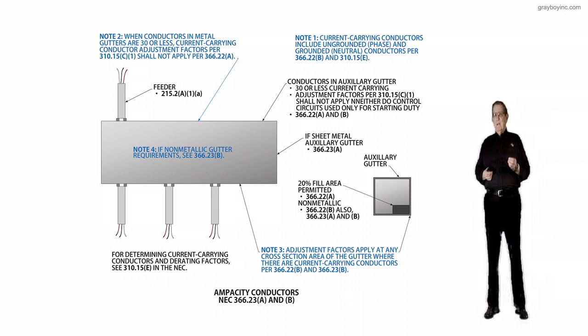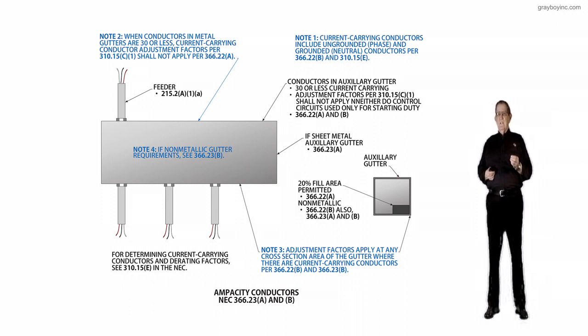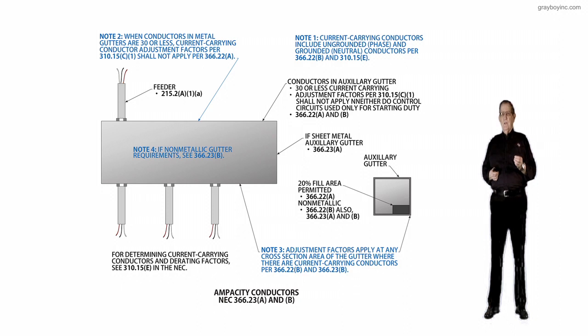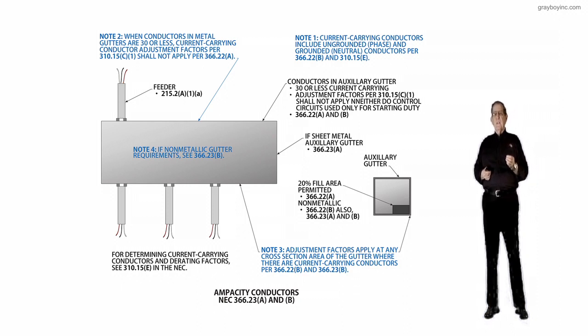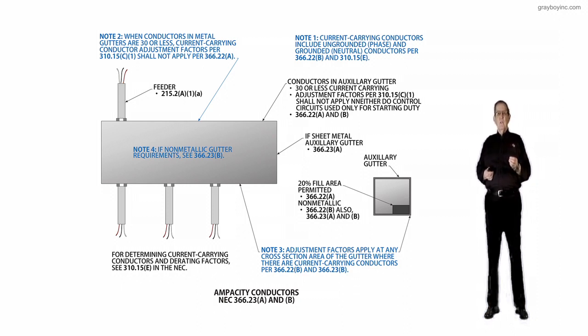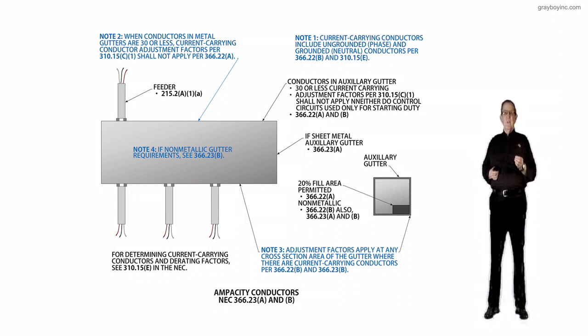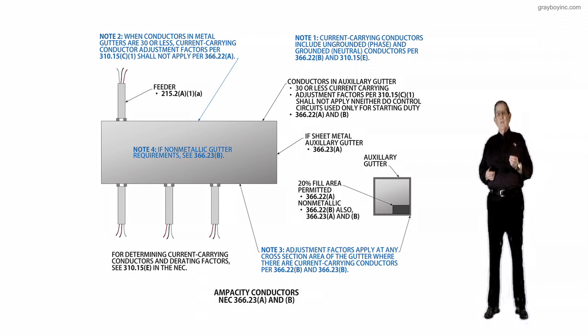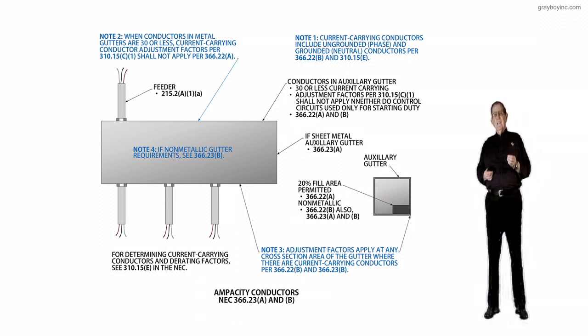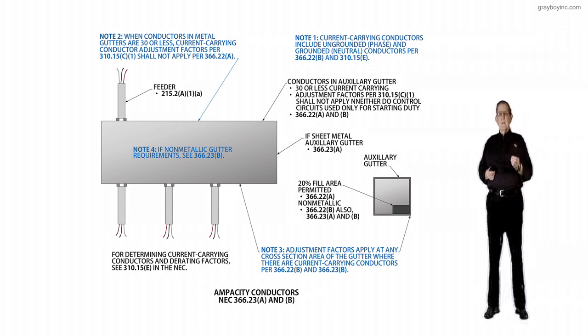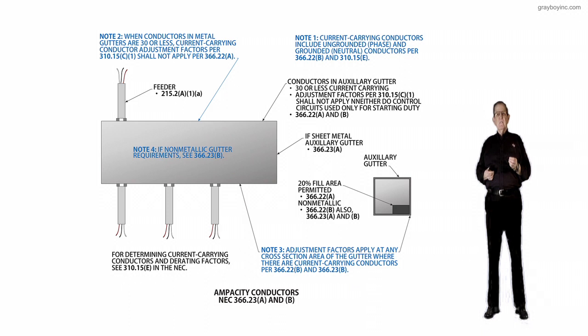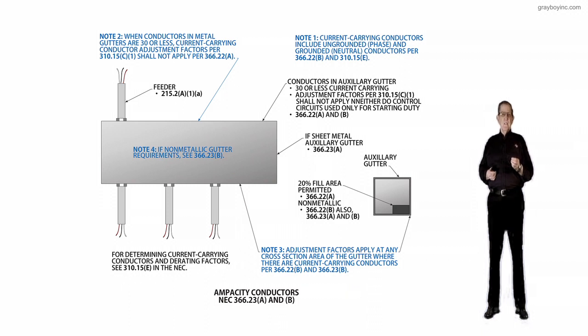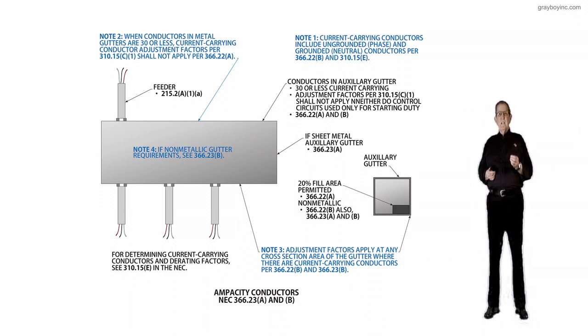The revision also clarifies that the adjustment factor required in 366.23A shall only apply where the number of current carrying conductors exceed 30 in any cross-sectional area of the sheet metal auxiliary type gutter. The adjustment factor specified in 310.15(C)(1)...